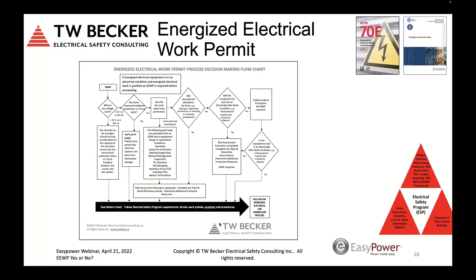But if we exempt these additional work tasks, there'd be 10 or 11 work tasks that are exempted. And then the other work tasks where it is truly repair or alteration, they would require the permit with justification, if there is justification. If not, we establish an electrically safe work condition, and then we do that de-energized repair or alteration work, which is the desired state for that work that I do want.